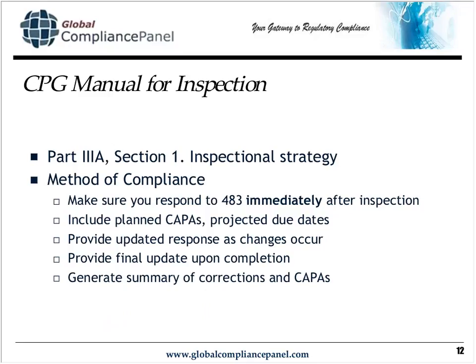And the way to assure this is to respond immediately after the inspection, specifically reference the CAPAs that you're going to implement, including the projected due dates, and as the changes occur, provide an updated response to the agency, and then a final update upon completion, and then just a summary.